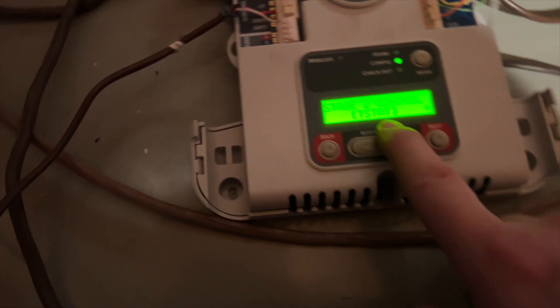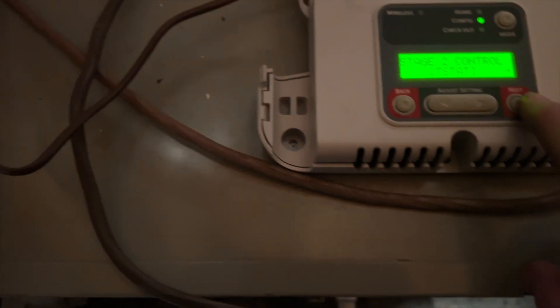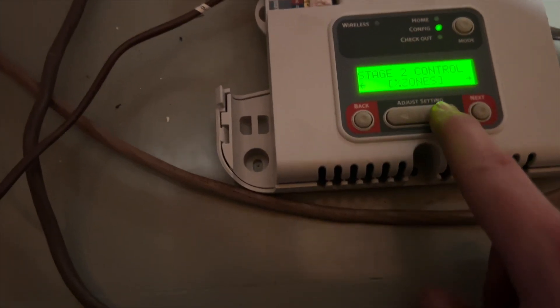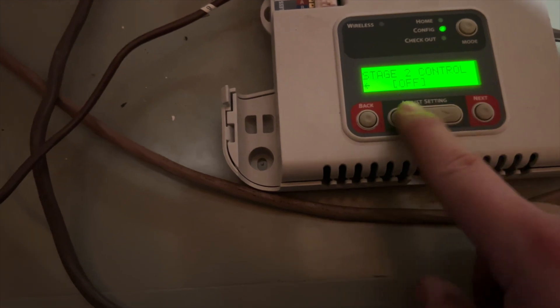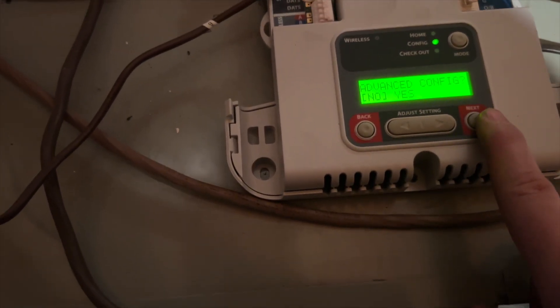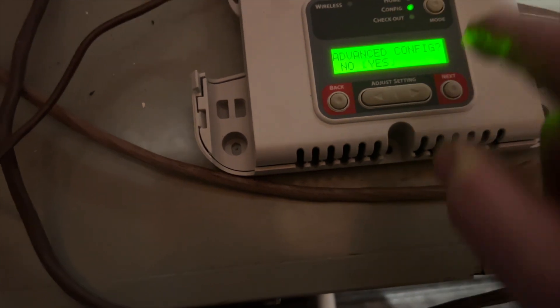Stage two control - do we want the thermostat to ask for it or do we want the zone board to ask for it? You can put it on a timer or you can do percentage of zones or you can just turn it off all together. We'll put it back on the thermostat. And now we can get into some more advanced configurations or you can skip it if you don't need to. But let's see what it looks like.